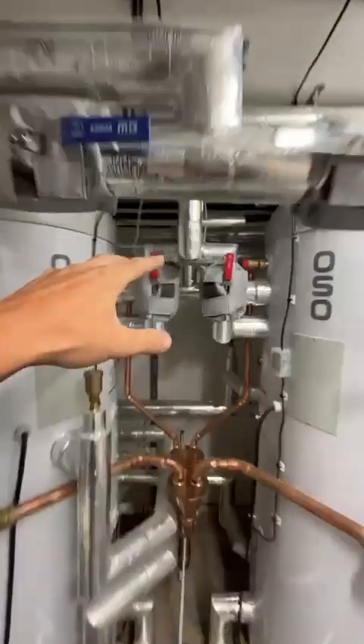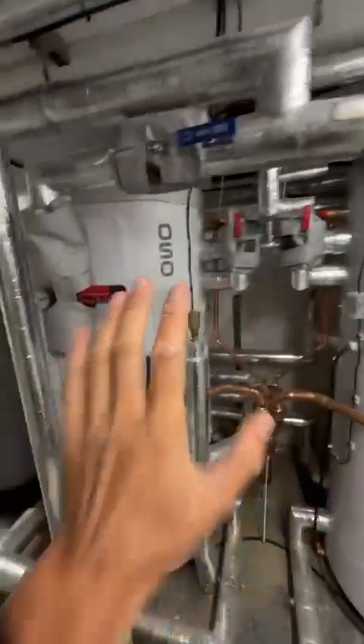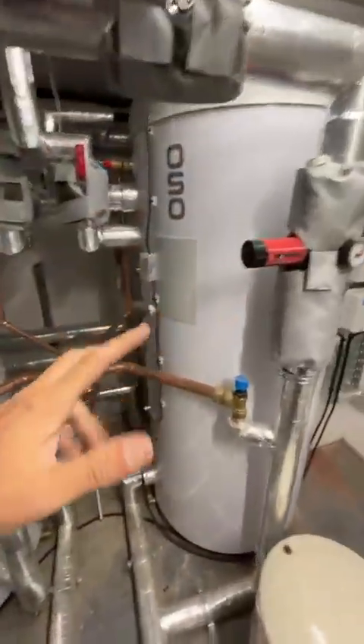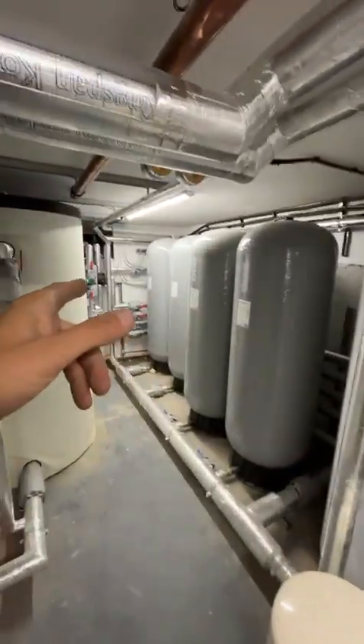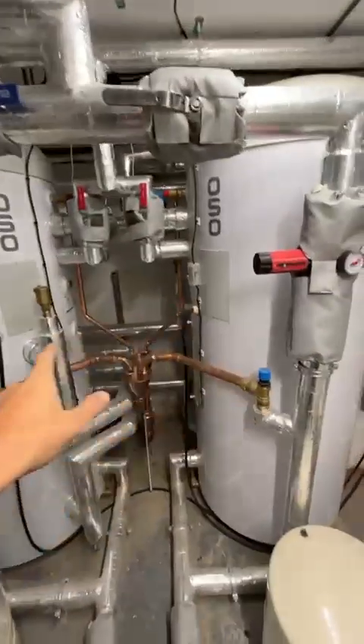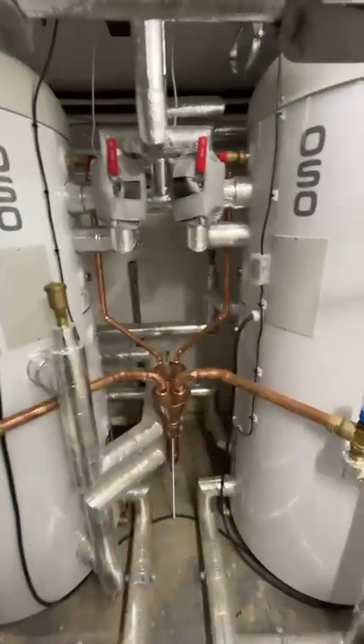That'll happen and we can then change them. So this is set up to do weekly, so we'll load this one week, then it'll swap to that one and take that straight up to 65, do a Legionella check, then it'll swap the week after, where we're getting heat loads run, sharing load through the heat pump and through cylinders, and keeping that water fresh and tanks clean. So that's what that'll do.